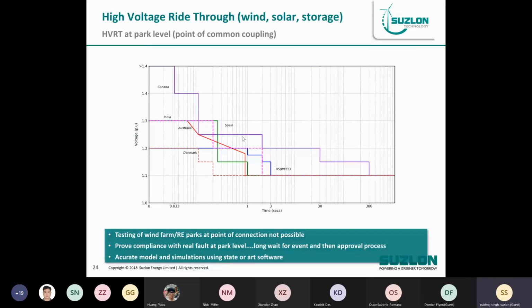The second critical requirement is the high voltage ride through. Although this happens very rarely - I haven't seen as many such cases compared to LVRT - there's still a very high requirement for high voltage ride through, where at the point of connection, the voltage can go as high as 140% of rated voltage and the turbine should still remain connected. In some cases, it should also absorb reactive power to bring down the voltage. But if you see the durations - 130% or 140% for 2 or 3 seconds - it's quite difficult to get even the electrical components to withstand such high voltage for such duration. So you need a customized design of electrical components which is not available off the shelf.